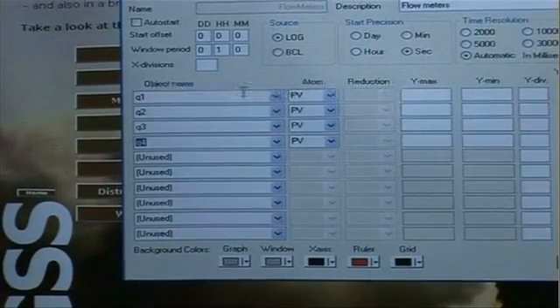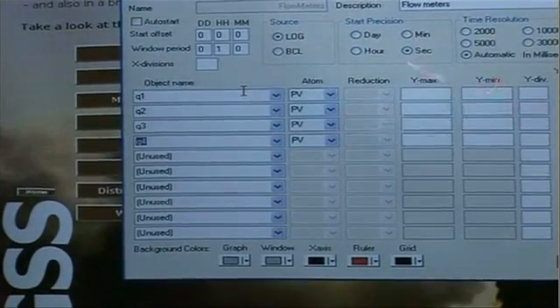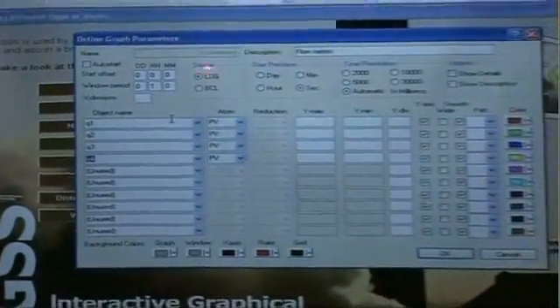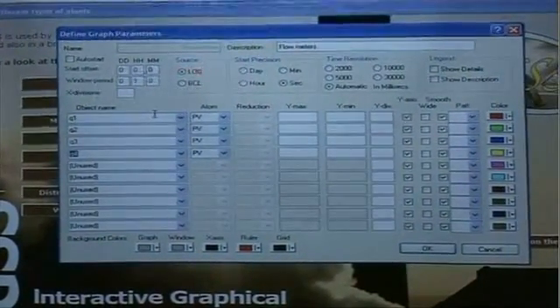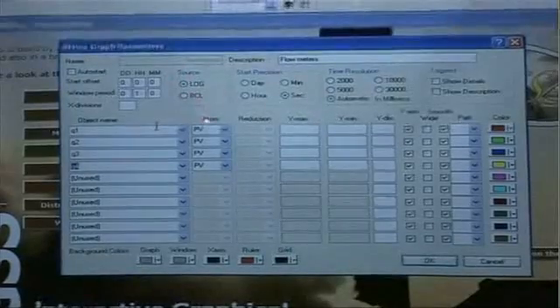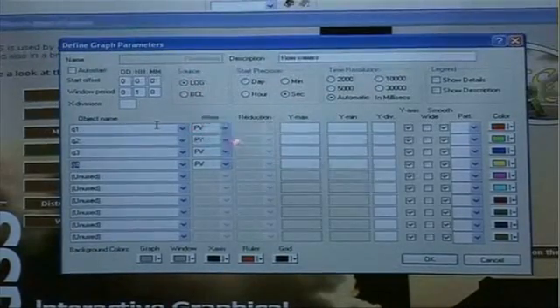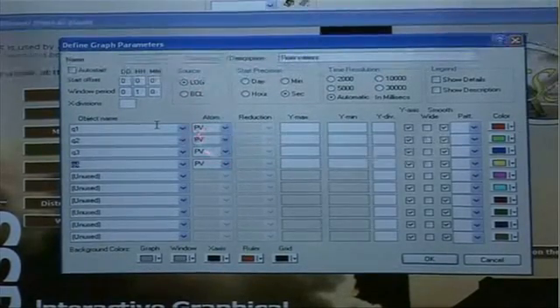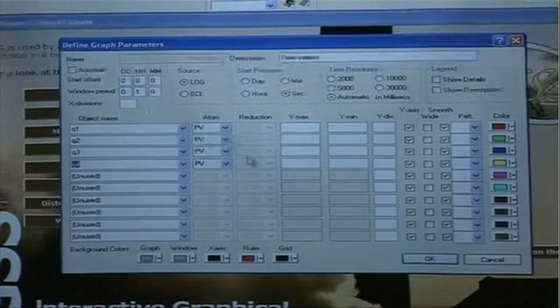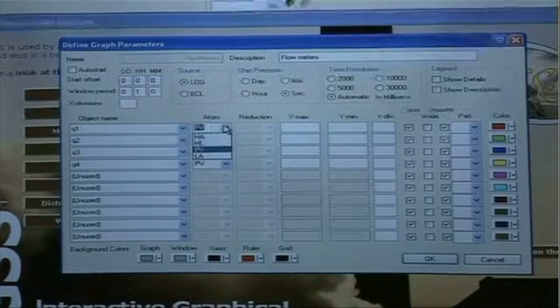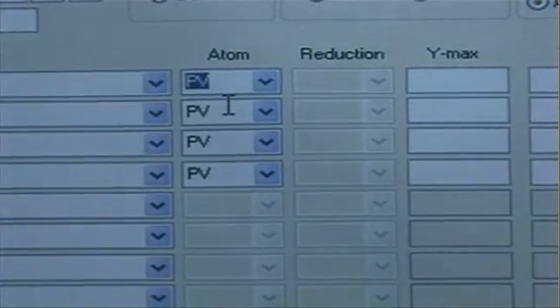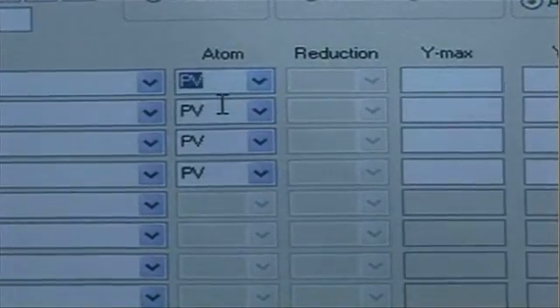As you can see the data source by default is log data and we'll keep this for this presentation. The other option is BCL. When I have selected log I can choose between the atoms that are enabled for this particular object. So in this case I have high alarm, high limit, process value and low alarm. And I'll select the process value. That's the one I want to show in my graph.